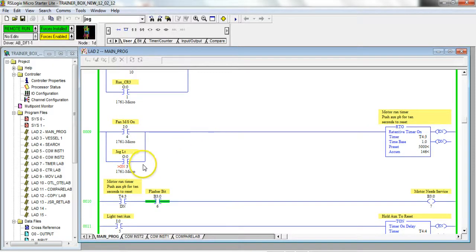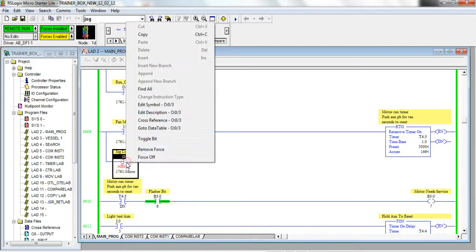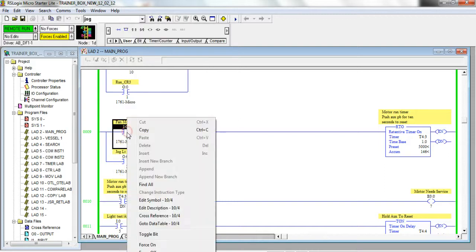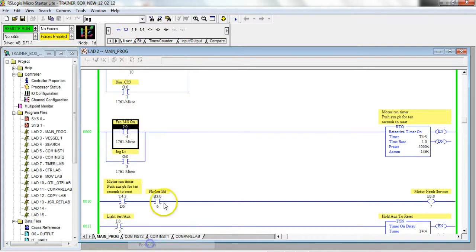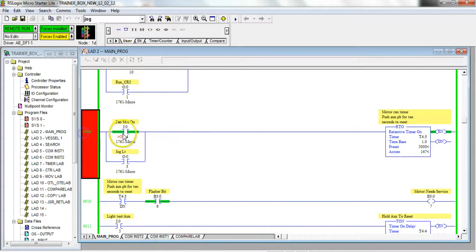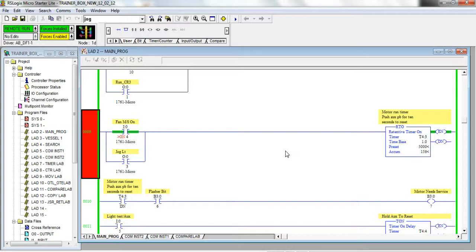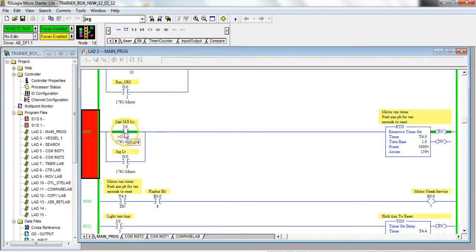So that's forcing of outputs and 'remove force.' Forcing of inputs - I would never recommend forcing inputs, because not only do you affect it everywhere in the program, but there's again no safeties. Any safeties you're bypassing that are built into the code. I can honestly say I don't think I've ever forced an input on.